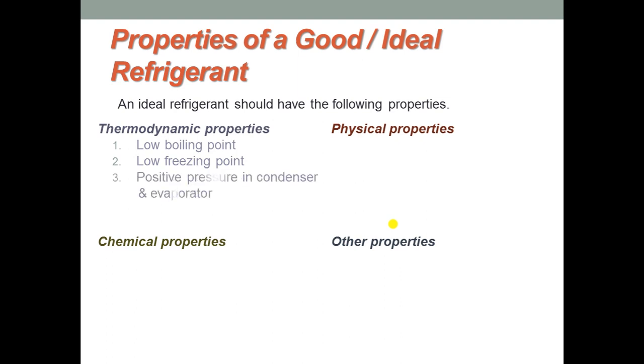The third thermodynamic property is positive pressure in condenser and evaporator. Then high saturation temperature, so that heat transfer can occur with the least possible circulating refrigerant. And high latent heat of vaporization and high critical temperature.